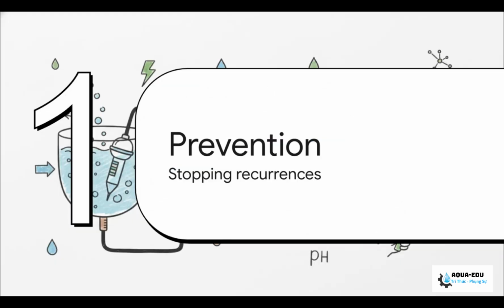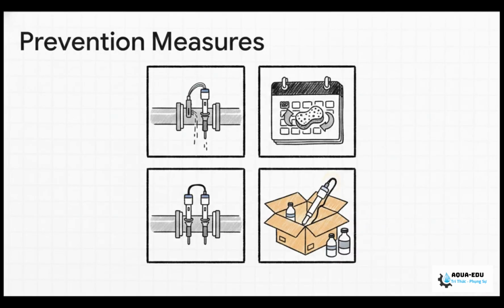All right, Section 5, Preventing Recurrence. Because let's be honest, prevention is way cheaper and a lot less stressful than a midnight emergency. If our inlet water is heavy with grease or sludge, we absolutely need to be utilizing auto cleaners like automatic jet sprays or ultrasonic cleaners. But even with those running, we must enforce strict weekly manual cleanings. For our most critical dosing points, installing a redundant backup sensor is an absolute lifesaver. And finally, always keep a spare combo probe, fresh calibration buffers, and 3 molar KCl in the warehouse. And check the dates. Don't let those buffers expire on the shelf.